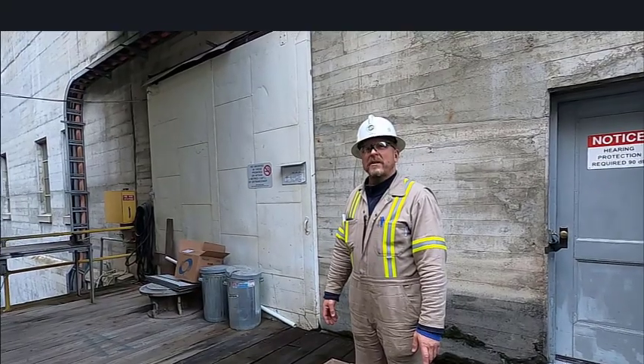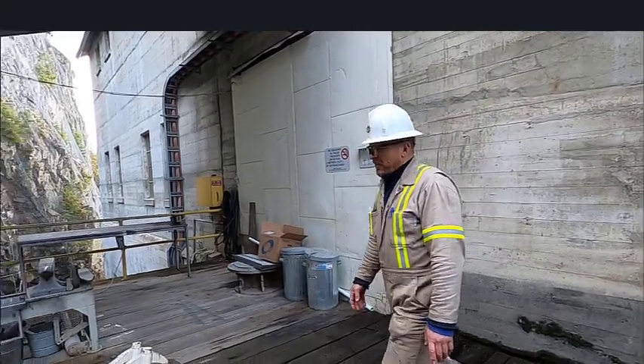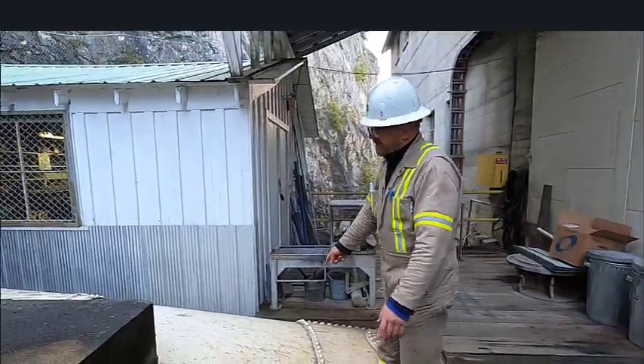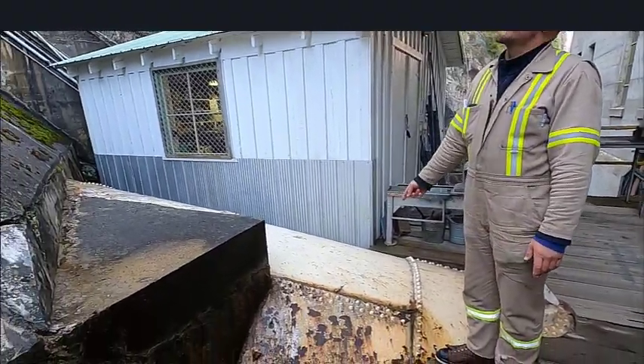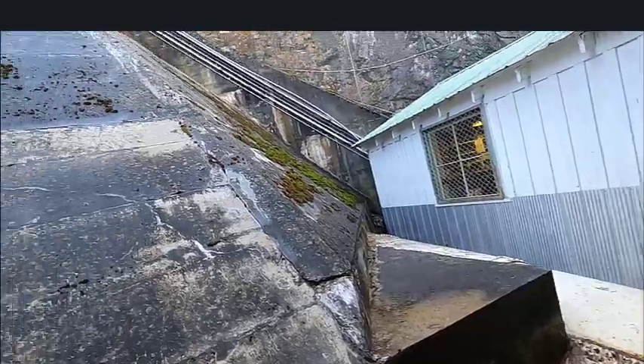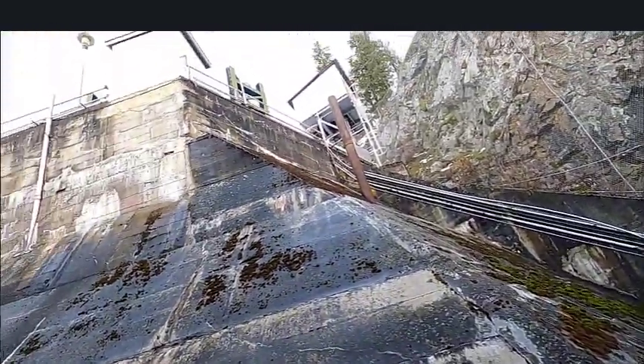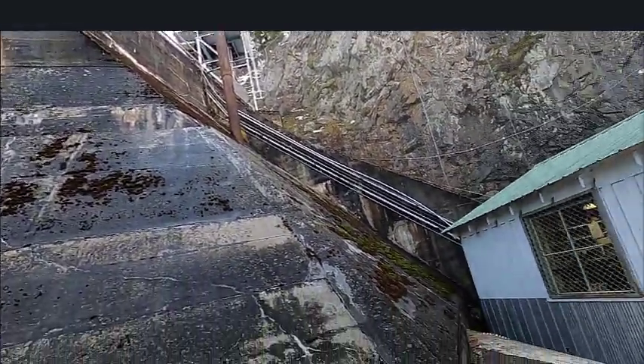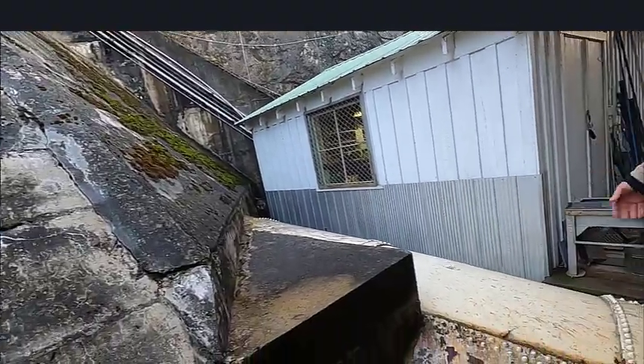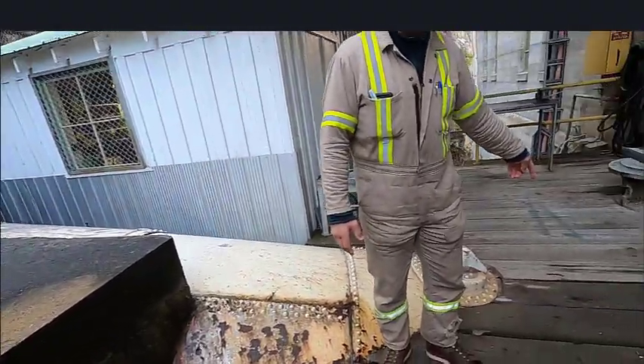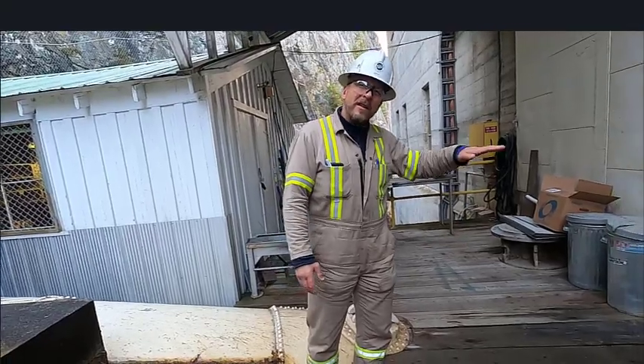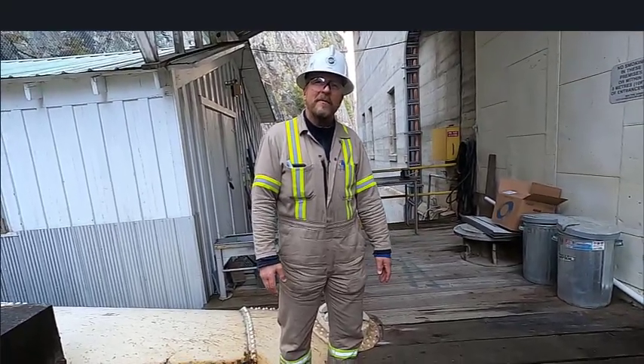Okay, we're down just outside of the powerhouse. So this large pipe here is what we call a penstock. It takes the water from the forebay through this pipe. This is for Unit 3. And this pipe is about 6 feet in diameter, and then it goes down at this point about another 20 feet to where the turbine is in the lowest level of the powerhouse.